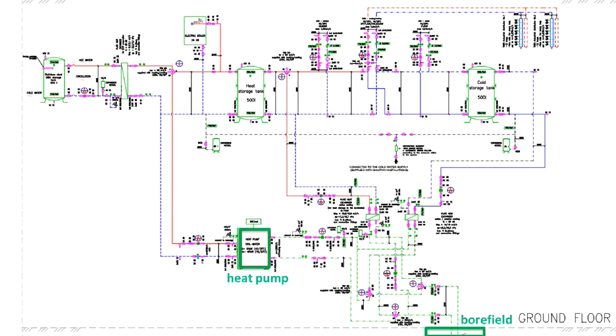If the heat pump is operated in passive cooling mode, the cold is taken from the boreholes, and without any compressor work of the heat pump, it is distributed to the cold storage tank. From the cold storage tank, it is further distributed to the air handling unit circle or again to the TABS circle. The heat pump can also be operated in active cooling mode. It means that cold is taken from the bore field to the primary side of the heat pump, and the surplus heat from the storage tank is sent to the ground again, or stored in the ground. I hope that it is clear. You will see it in the afternoon.